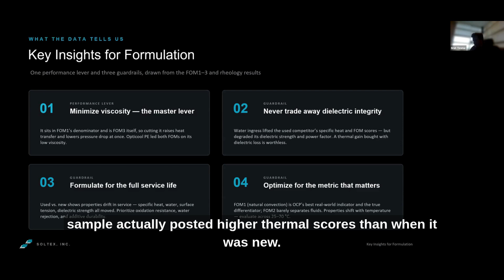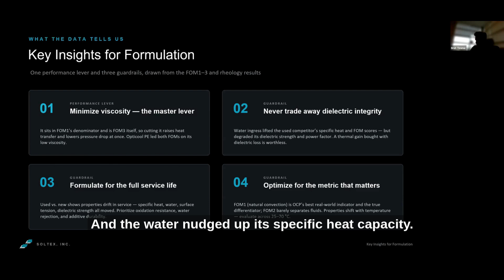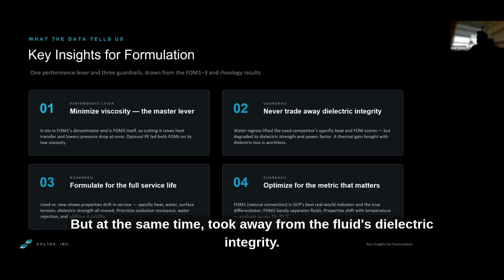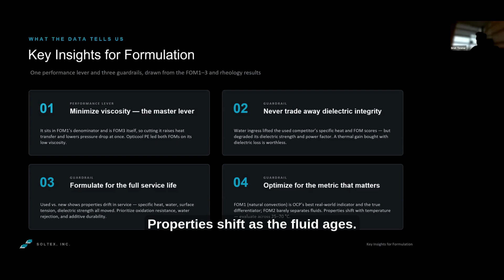The used competitor sample actually posted higher thermal scores than when it was new. The reason is that it had absorbed a lot of water in service, and the water nudged up its specific heat capacity, but at the same time took away from the fluid's dielectric integrity. That's the trade-off you can expect in a fluid that's in service - it may get more effective at heat transfer, but sacrifices its dielectric integrity to do that. Secondly, we want to formulate for the full service life, not just a brand new fluid on day one.